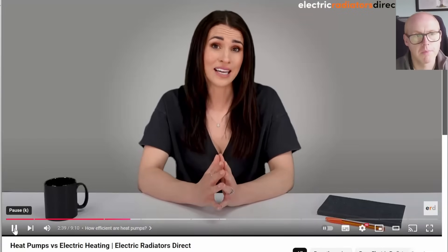Secondly, it's vital your home is well insulated if you want to maximise efficiency. If not, you'll be waving goodbye to any potential energy savings. This thing about insulation gets paraded all the time. At the beginning of the video, you chose to say that we need to upgrade radiators — which is fair — but now you're talking about upgrading insulation. You don't need to do both. It's about designing for the correct temperature and getting the correct emitters so that your heat pump can run at a low flow temperature. This can be done through one of two methods: you can either upsize your radiators to run at a low flow temperature, or you can increase your insulation levels and not necessarily need to increase your radiator sizes. So maybe pick or choose one of those.